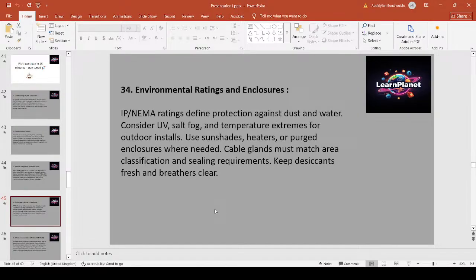Environmental ratings and enclosures. IP and NEMA ratings define protection against dust and water. Consider UV, salt fog, and temperature extremes for outdoor installs. Use sunshades, heaters, or purged enclosures where needed. Cable glands must match area classification and sealing requirements. Keep desiccants fresh and breathers clear.